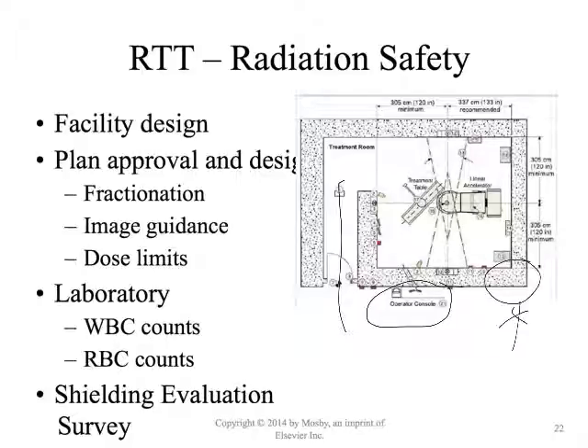We also do shielding evaluations. So I mentioned that they had to keep a radiation dosimeter there outside of that treatment vault. How did they know it was leaking radiation? Well, they did shielding evaluations where they go around with giant pieces of film and measure if there's any radiation coming out of that treatment vault whenever they make exposures.